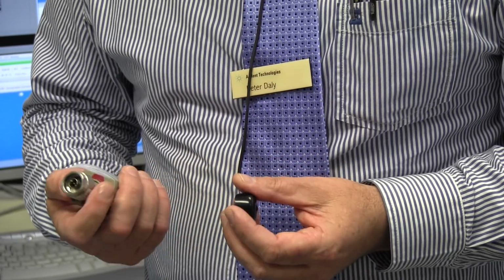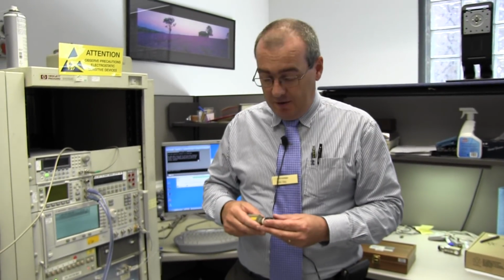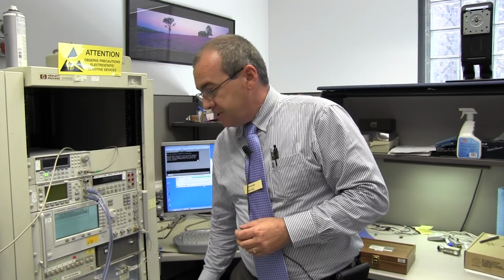Some people will tell you the best way to calibrate this sensor is to hook a reference sensor up to a source and measure it, then compare your results, which is one method of calibration. We actually have a system in place that is a NIST system, which uses 3 sensors. NIST being the National Institute of Standards and Technology in the United States, their National Measurements Laboratory. So we use a NIST-approved system, which was developed by Agilent.